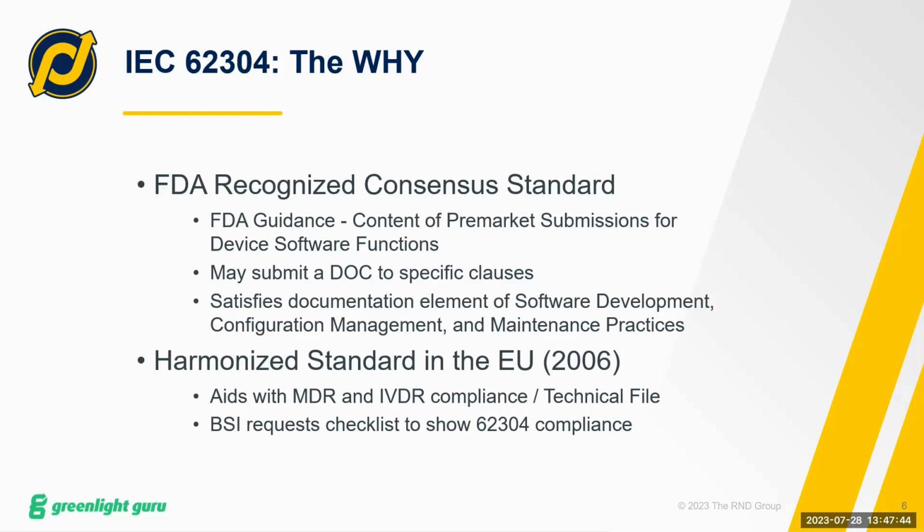Now, the EU has harmonized the 2006 version, but I've heard that notified bodies are advising medical device manufacturers to go ahead and use the current version of the standard. And by using it, it aids you with what you need to submit in your technical file. And also, a while back, we had a client who was going through to get a CE mark, and they were working with BSI, and BSI wanted a checklist to show that they were compliant to 62304.